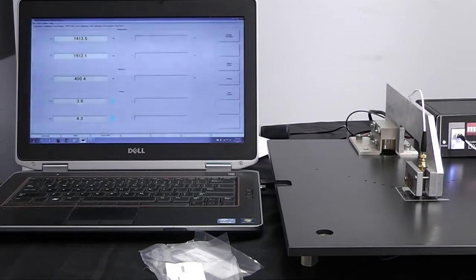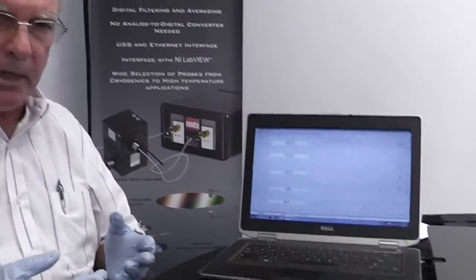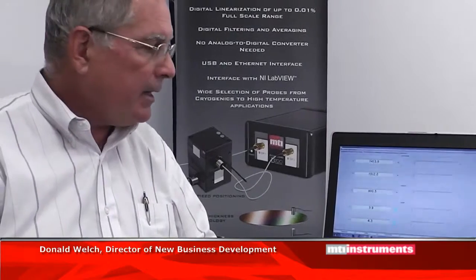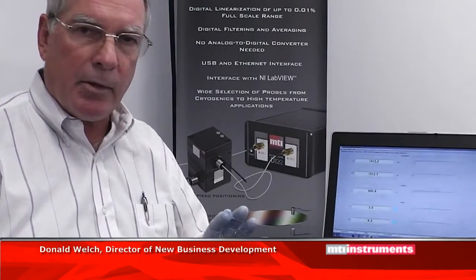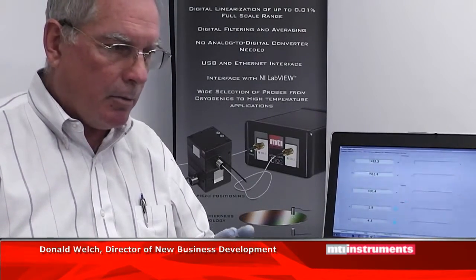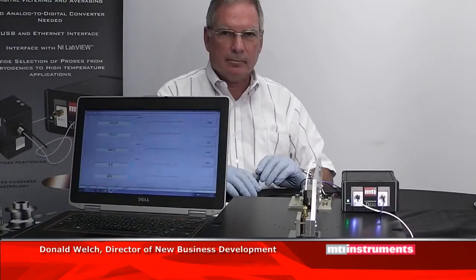So what we've seen here in this tutorial is that we can measure a variety of different non-conductive materials, such as sapphire wafers, plastic, which could be in process, and we've also looked at Gorilla Glass, which is, again, a dielectric and non-conductive material. And we get very good accuracy with what we're seeing here. It's within 2 to 3 microns of what it's supposed to be, and if you're very careful with the cleanliness and setup, you can get down to typical accuracies of less than a micron.